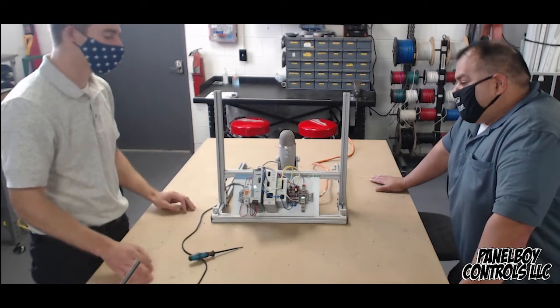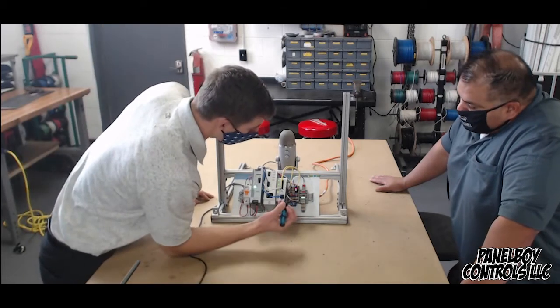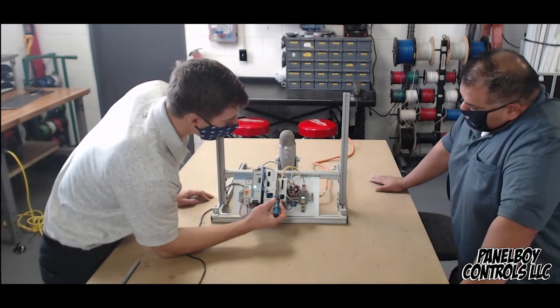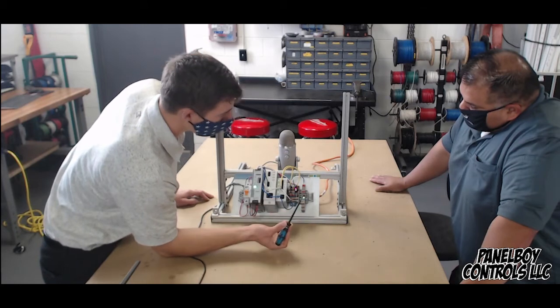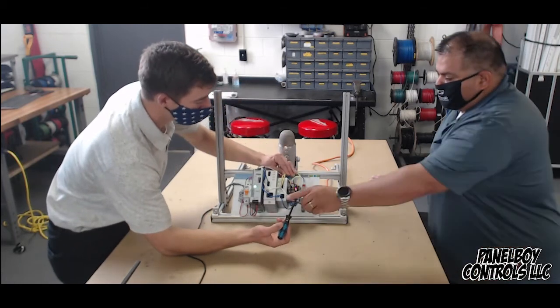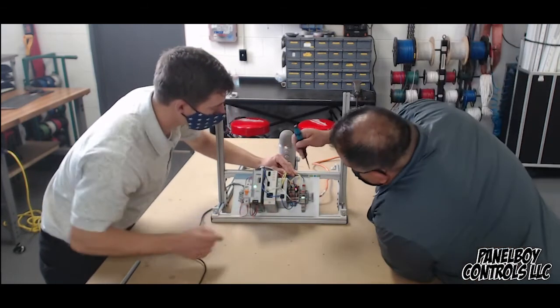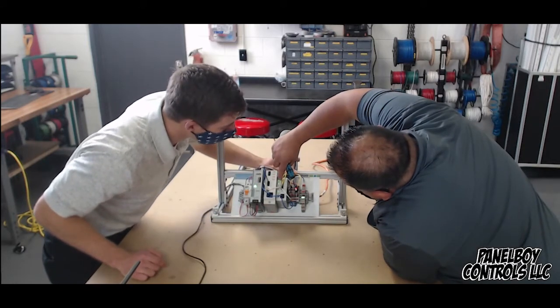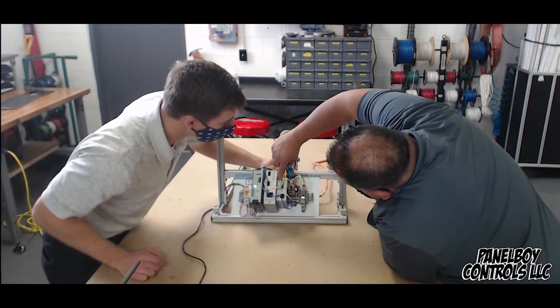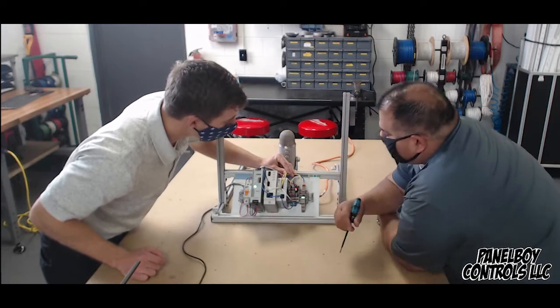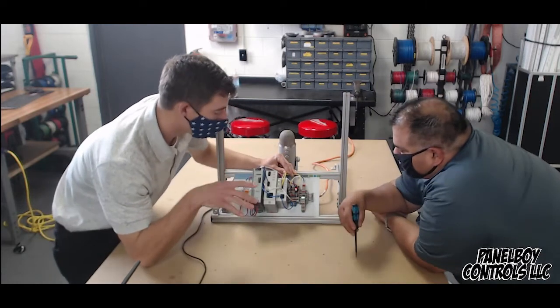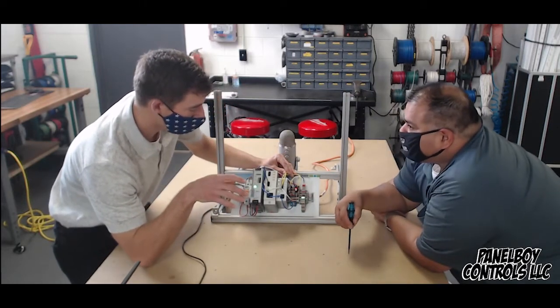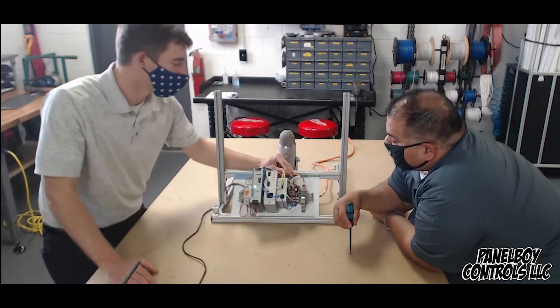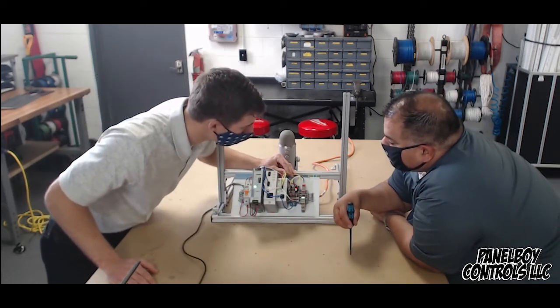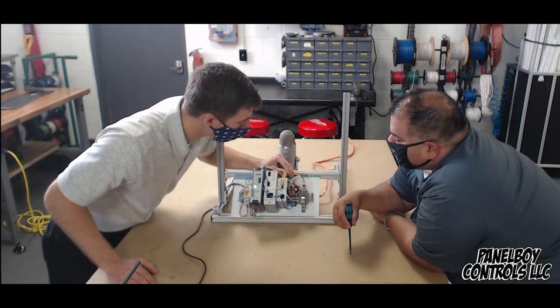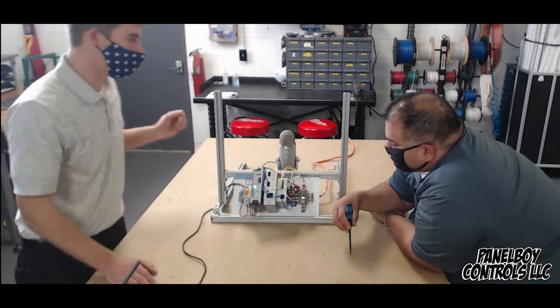You don't want that, that's expensive. So instead, to set this you press and hold - you can do it with your finger or a screwdriver. You press and hold and it starts to blink. The number of times it blinks consecutively before pausing is what it's set to. Currently we've got 1, 2, 3, pause, so it's set to 3 amps. Does that make sense?